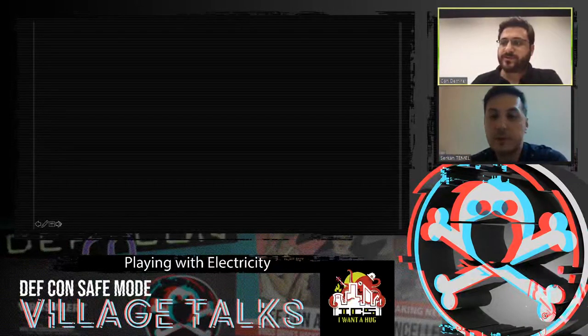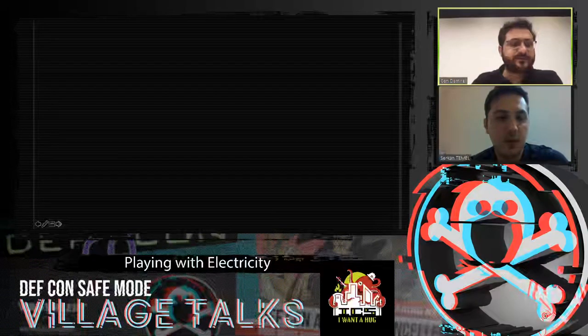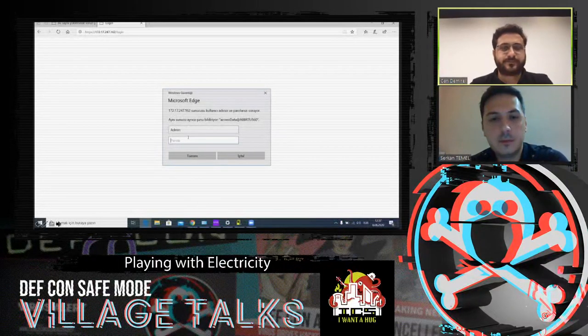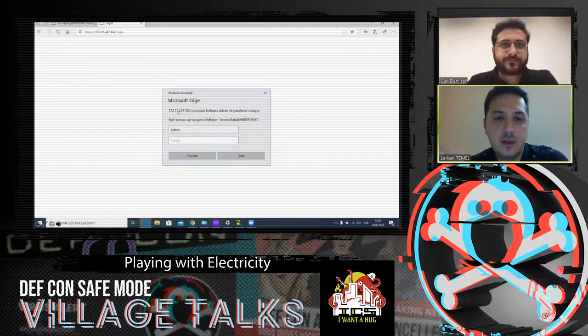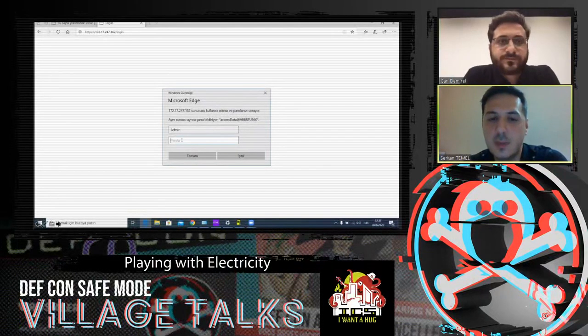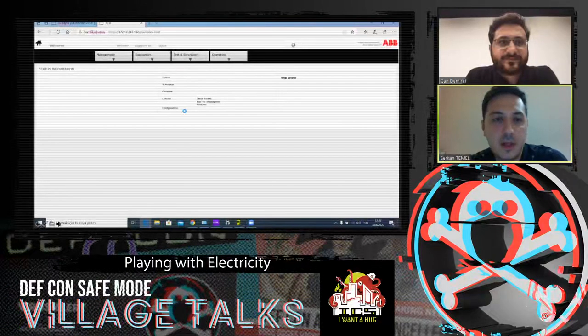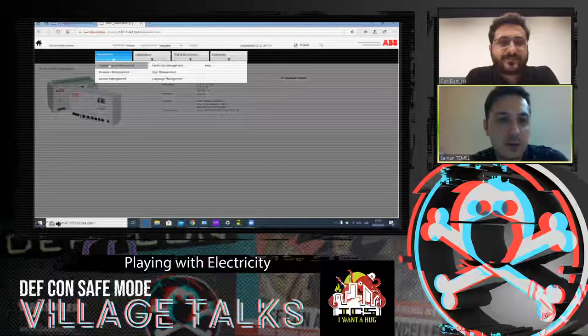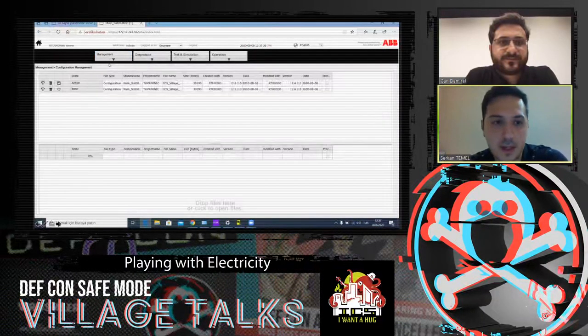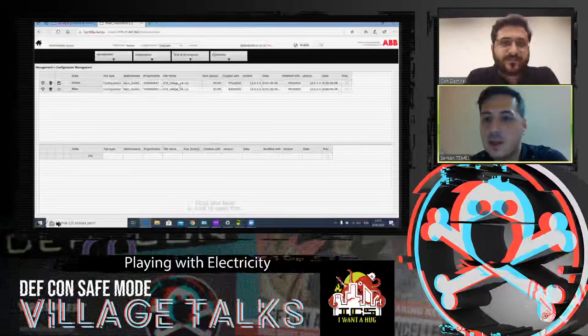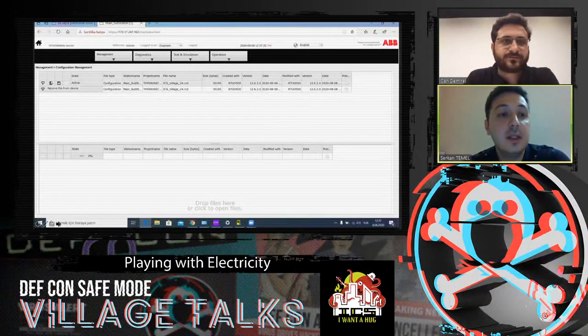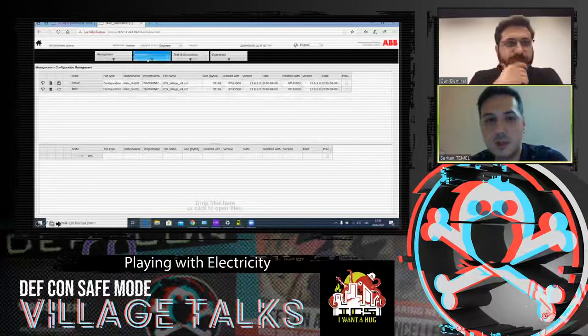So we can jump into the second one. In this record, we directly connect to the RTU web interface. As you see, this is the IP address of the first Ethernet interface, and we use a username and password. On that site, you can easily see the configuration management page. You see the configuration file, which configuration is now active. You can update this configuration file, get the configuration file from the device, delete this configuration, etc.